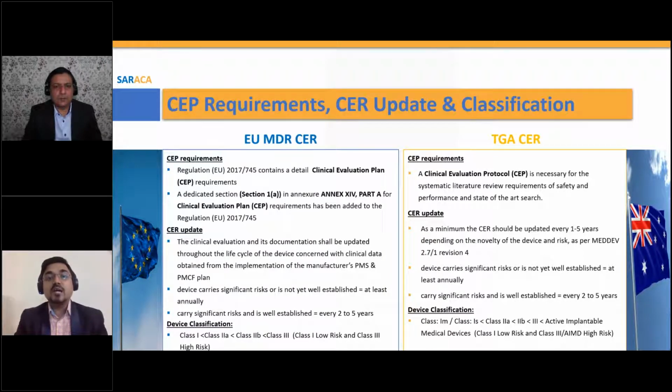There should be a clear purpose and scope inside the clinical evaluation plan. You need to address the risk management reports and how you are doing the risk management, risk analysis or risk assessment. You need to define the plan so that you can describe those risk-benefit analysis details. You can describe those in the report, but in the plan you need to list all those residual risks, your risk management plan, risk management report, then user training related reports and data. You need to list all the things which you are going to define in the clinical evaluation report.